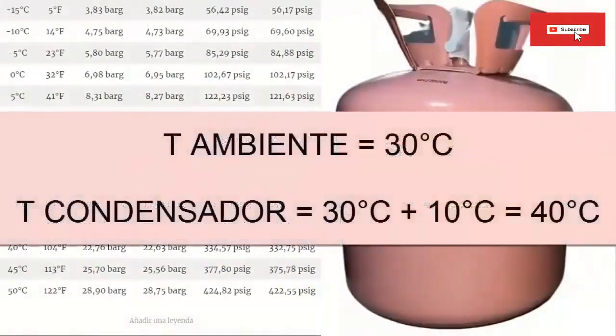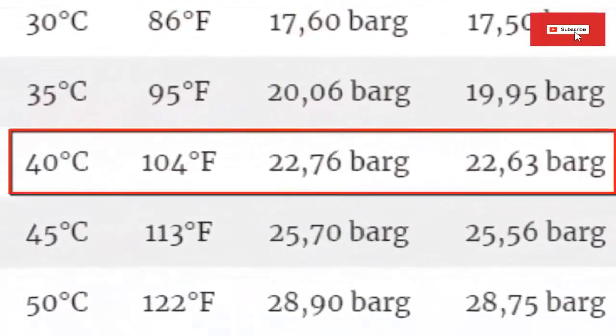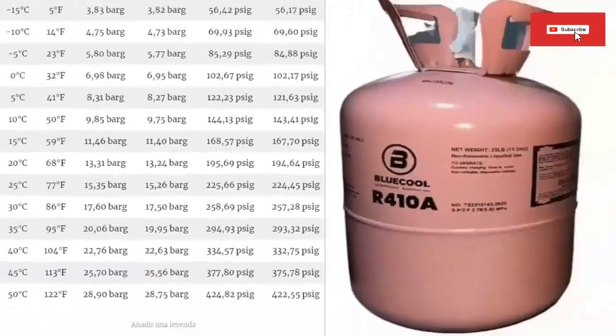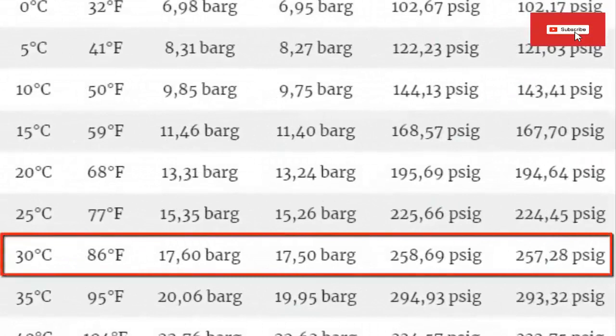For an outdoor environment temperature of 30°C (86°F), and considering that the condenser temperature on average exceeds the ambient value by 10°C, then the condenser temperature is 40°C (104°F). Looking in the table for this temperature value, the condenser pressure, or high-side pressure, has a value of 22.63 bar (332.75 psi). When it is necessary to know the pressure of the equipment when turned off, the pressure value is searched in the table. For 30°C (86°F), the equipment pressure at rest is 17.50 bar (257.28 psi).